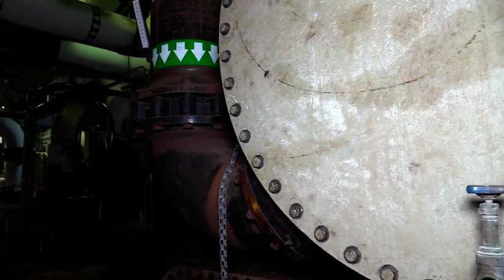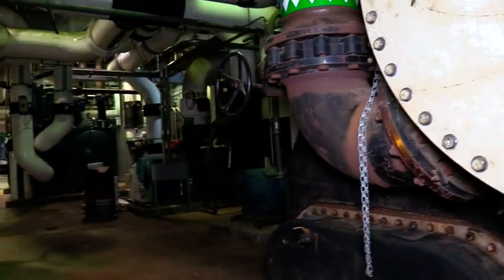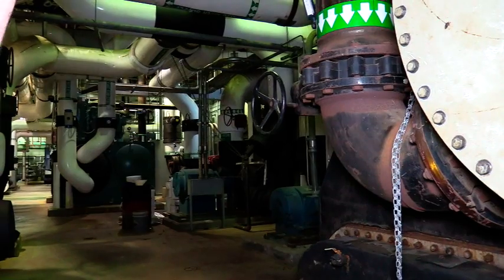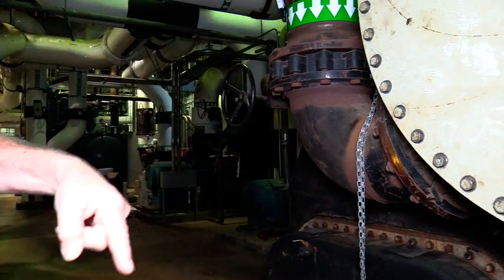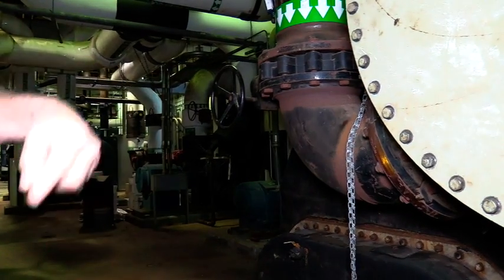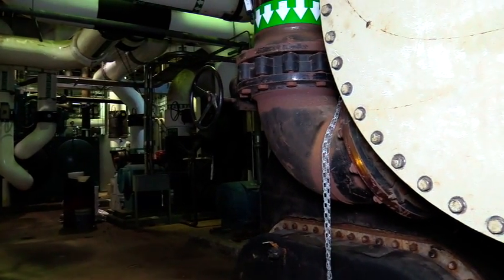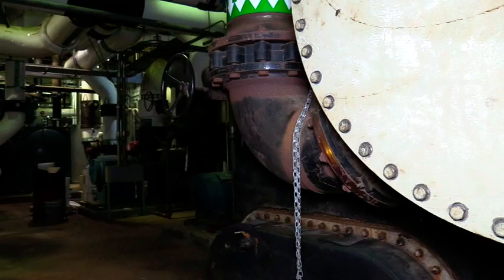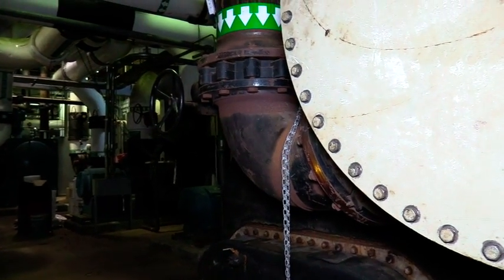So if you get a surge, there's a few things that cause that. It'd be like the condensing water temperature got too high, and that causes a surge. If the load gets too low, it'll surge. And if it gets air in it, it'll surge. You can hear it when it surges.